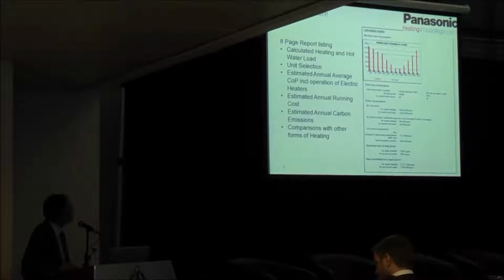And that report will give you the heating and hot water load for the year. It will give you an average COP for the full year, so it's not just looking at the design condition of -5 or +2. It's looking at it for the whole year for wherever your unit is located. And then it gives you estimated annual running costs plus your carbon emissions, and compares that to other forms of heating.